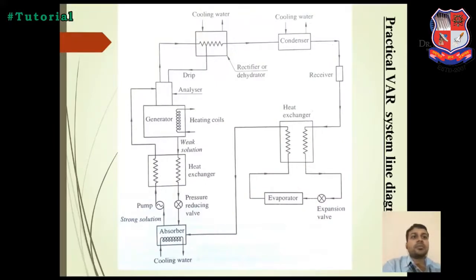This is the line diagram of the practical VAR system. In the last video we completed the two main components. So for the simple VAR system, the aqua ammonia VAR system, the components are generator, condenser, expansion valve, evaporator and absorber. We have to study them in detail. The first part of the practical VAR system is the generator. You have to give external heat to the generator, by an electric system, meaning a heating coil, by any waste heat rejected from plants, or by heat from solar energy for heating up the generator.